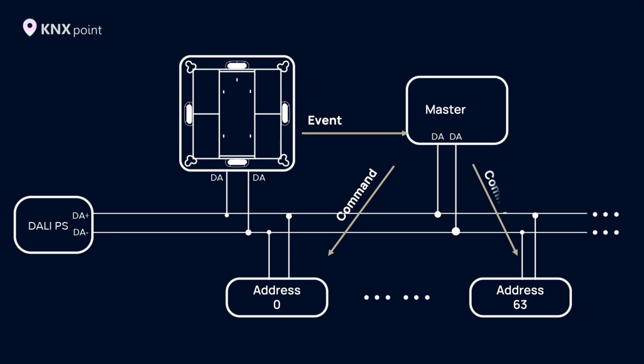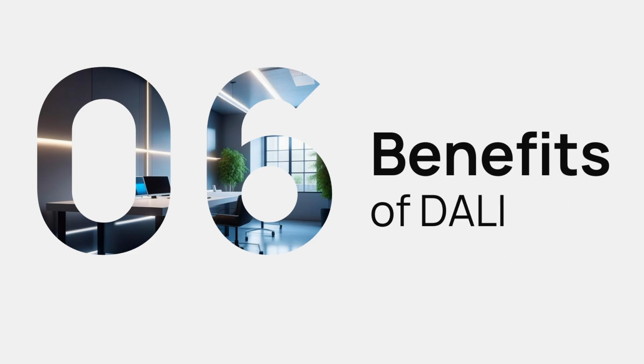A master controller is mandatory in a DALI 2 system. Configuring such a system is more complex, but it offers more functions due to the use of scripts. It is also important to note that DALI 2 requires special command devices, buttons, sensors, while the actuators will be the same as in a regular DALI system. Let's examine the advantages of this system at different levels.